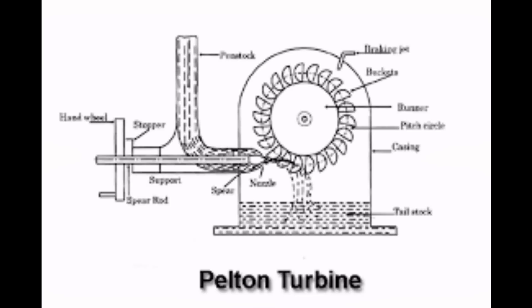With the water turbine, what we need is speed of water. So we can either go for mass or we can go for momentum — one or the other. That's appropriate to your situation: if you live somewhere where you have access to a low supply of water but it has high momentum, that's the better way to go. If you're somewhere where you have an awful lot of water moving slowly, then the Kaplan type is the one to go for. You're not stuck with that though — you can change a mass of water into fast-moving water, which is exactly what a Pelton wheel does. Vortex turbines work with a mass of water at a low head, but by getting it into a vortex they're trying to get some momentum in there as well — sort of half and half. In its essence, what matters is it's either mass or momentum, and you choose a turbine suitable for that.